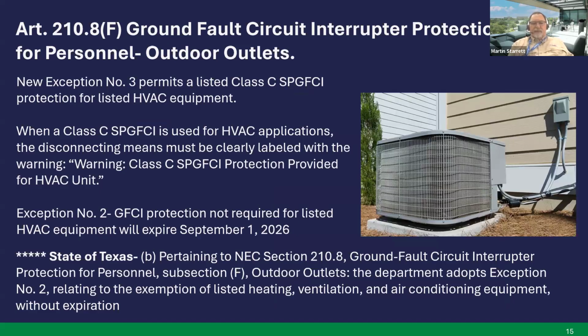Okay. Also, as a lot of you know, we've had this whole HVAC GFCI protection issue going on since the 2020 code. In this particular article, they did add a new exception, number 3, that permits a listed Class C special GFCI protection for listed HVAC equipment, along with Class A. But if you use one of these Class C special GFCIs, you have to label the disconnect with a warning: Class C special GFCI protection provided for HVAC unit.